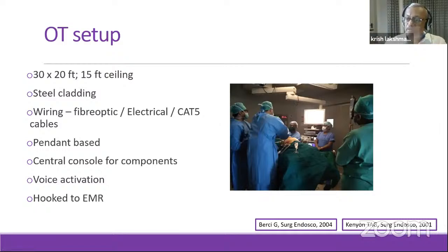And they have to be 360 degrees rotatable, because if the surgeon is standing to the left of the patient, the monitor is to the right. What if you're standing between the legs of the patient? The monitor has to come here, where the anesthetist is. If the surgeon is standing next to the anesthetist at the head end of the table to do a pelvic operation, the monitor has to go to the foot end of the table. So these pendants and their movements have to be versatile enough that everything can go all the way around.